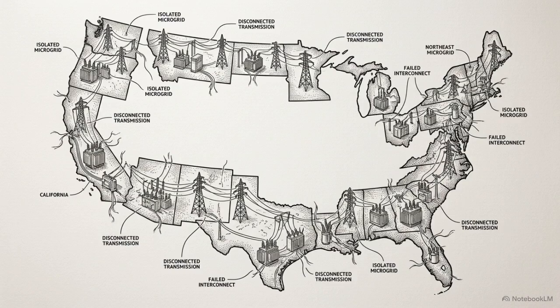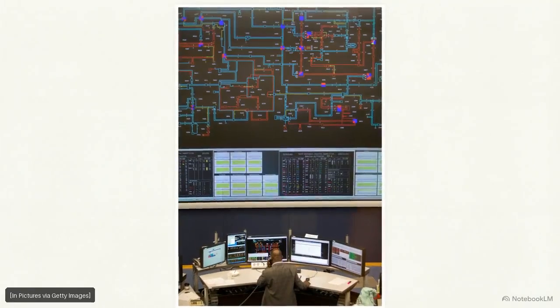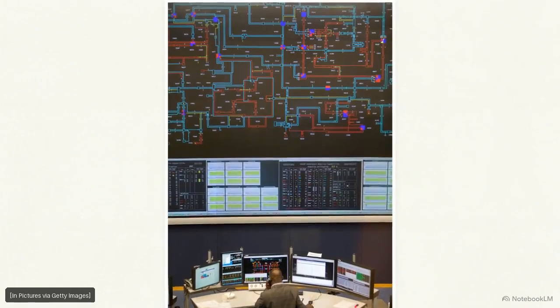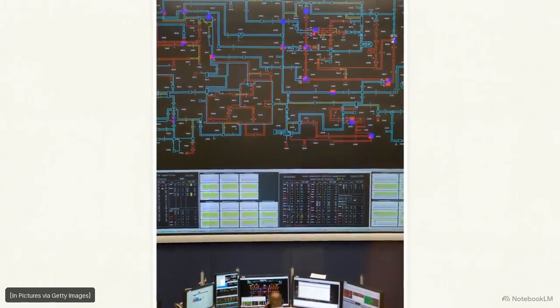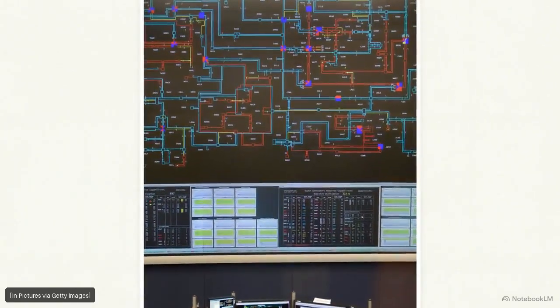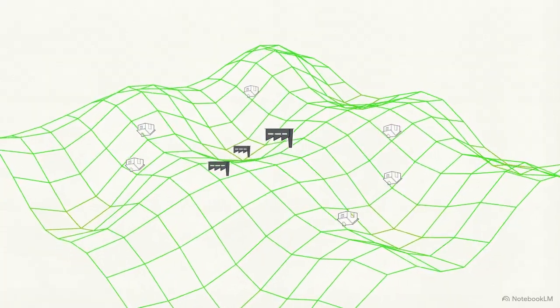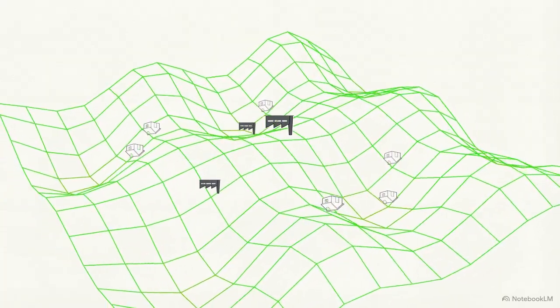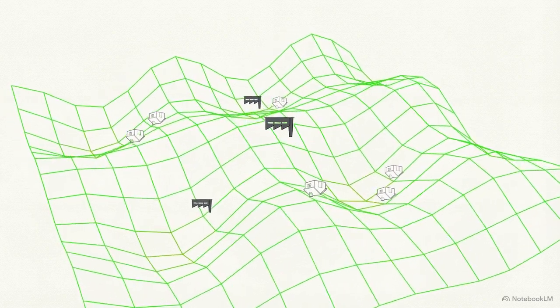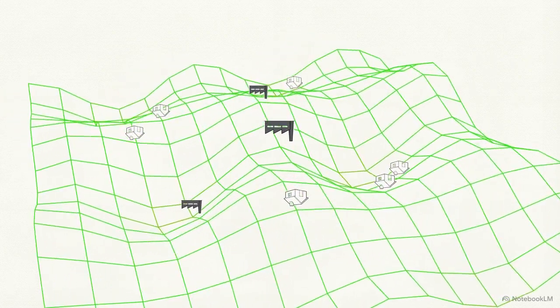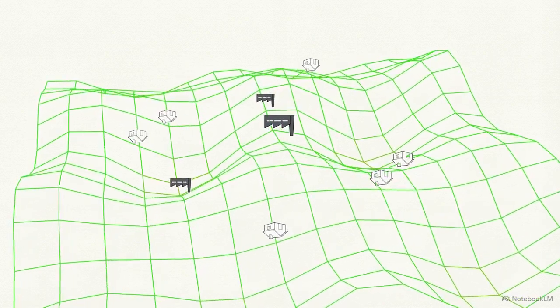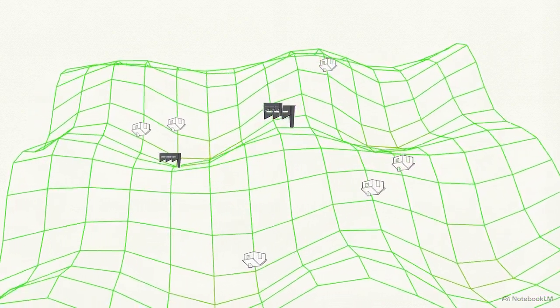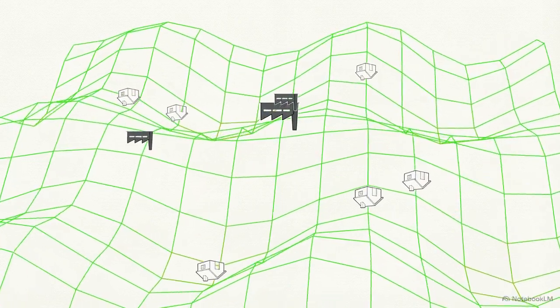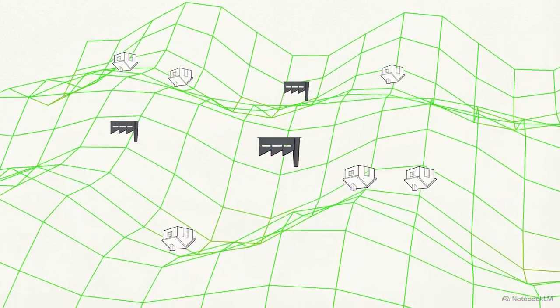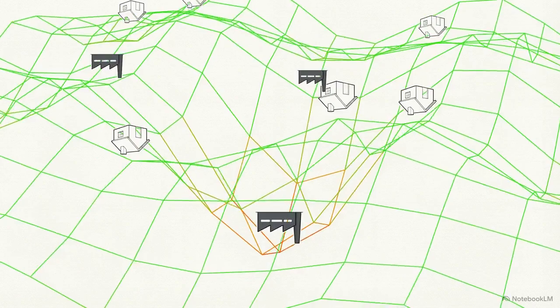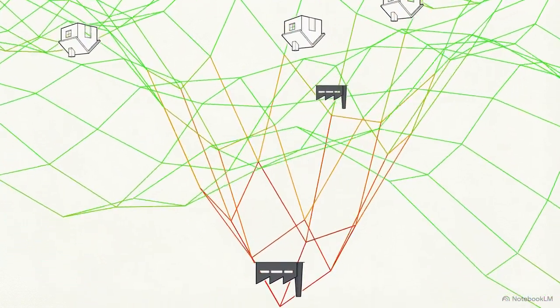Because distance is so destructive to voltage, grid operators have to abandon the idea of a single, uniform power system. Instead, they manage the grid on a strict, localized, zonal basis. They view the grid as an invisible topography, almost like a mountain range. It's called a voltage profile. Voltage levels constantly dip and rise depending on the specific generation and demand happening in a given neighborhood at that exact instant. A dense cluster of heavy manufacturing plants or a massive data center will actively drag the local voltage down, carving a deep, dangerous valley into that topographical map.